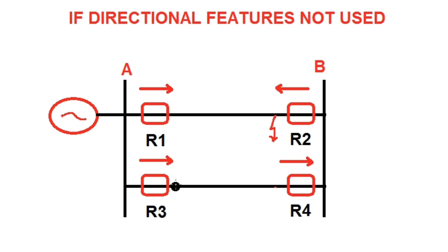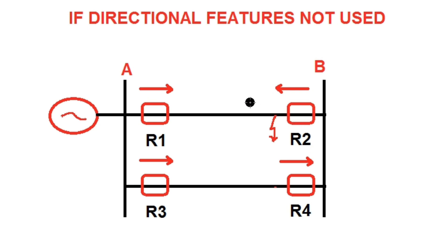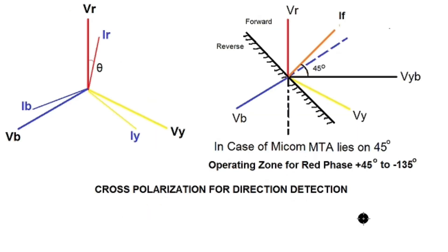Now consider another case where in between substation A and B there exists a double circuit line. The source is connected at substation A end. If a fault occurs in one circuit, only R1 and R2 should operate. However, R3 and R4 will sense the same current and, without directional features, will also operate and isolate the healthy parallel circuit from the system. So directional relay is used for lines with sources at both ends and also for parallel circuits.